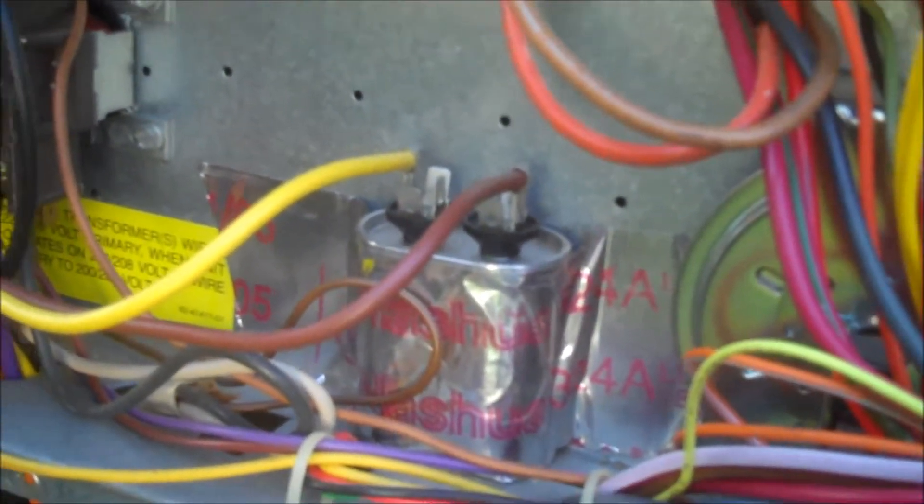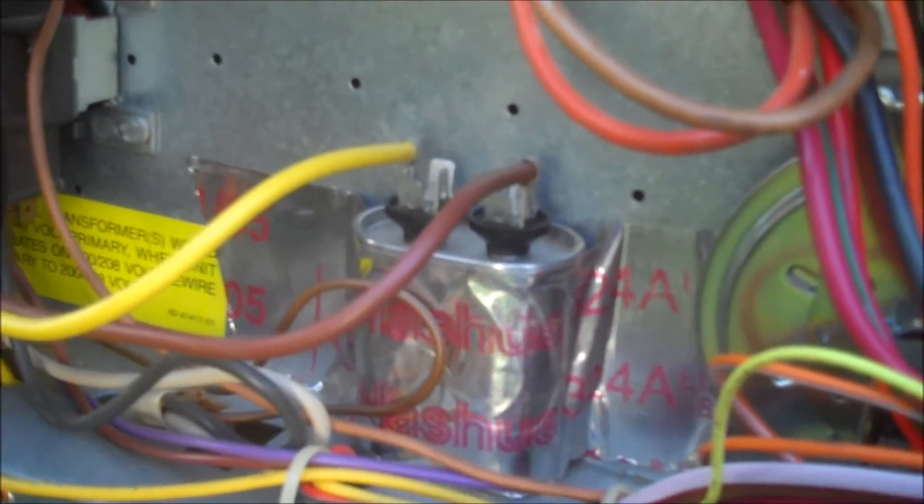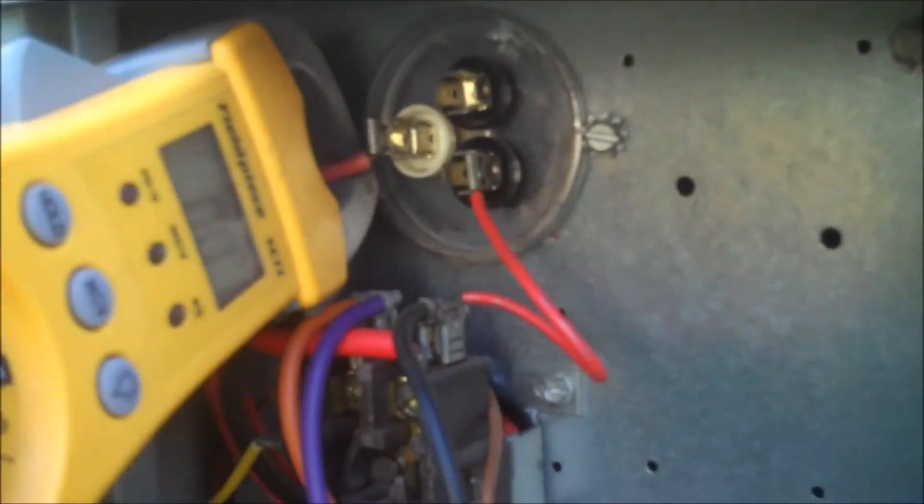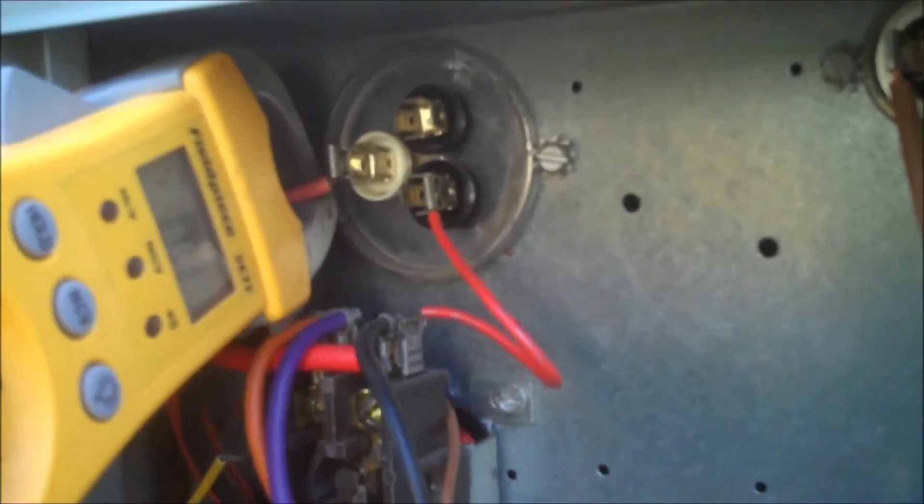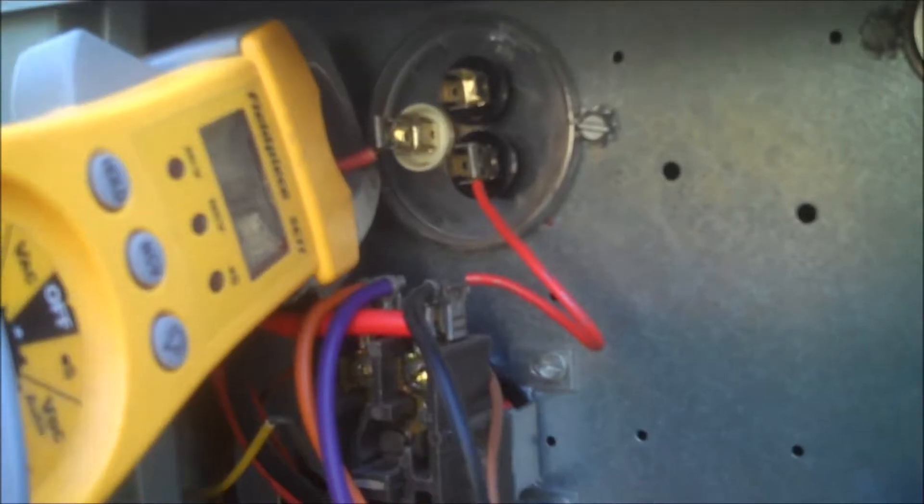Alright, we've already checked all the capacitors. In this case, somebody has patched in a small fan capacitor instead of using the other side of the dual capacitor there. But they both check out.